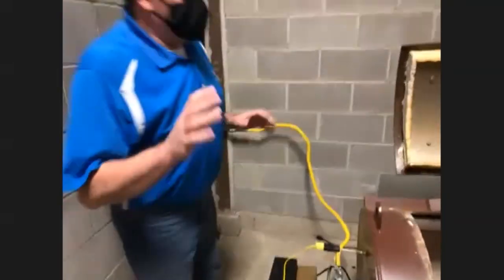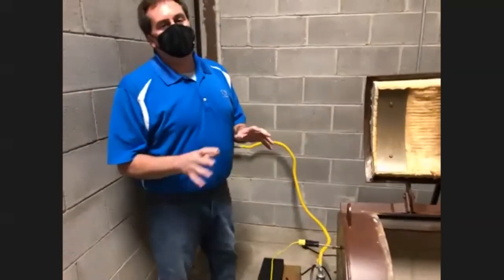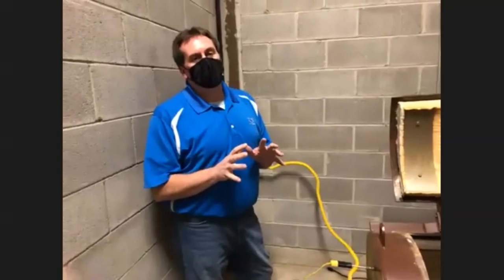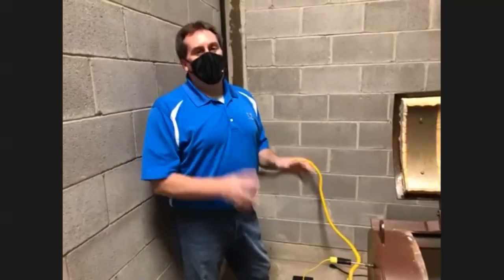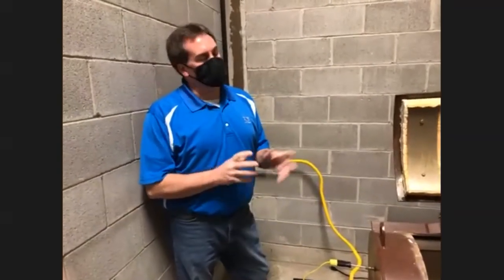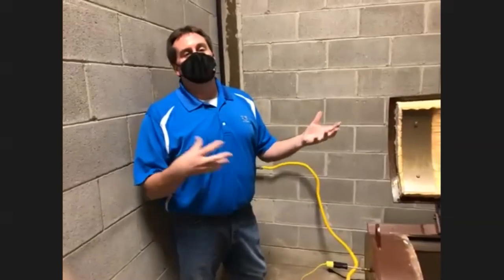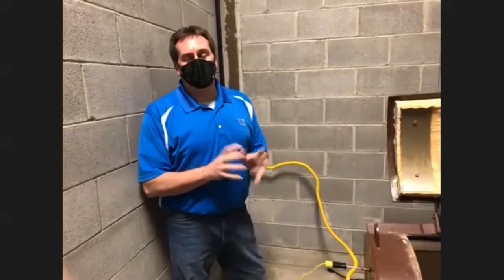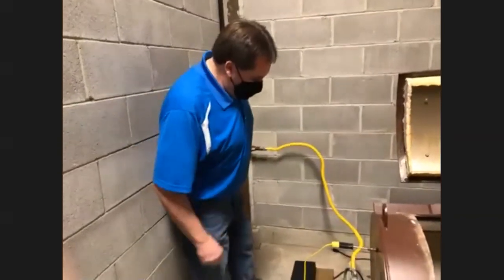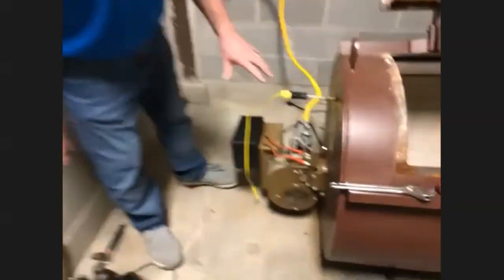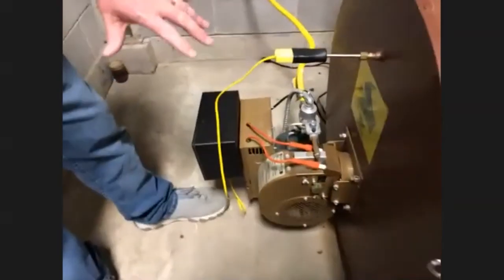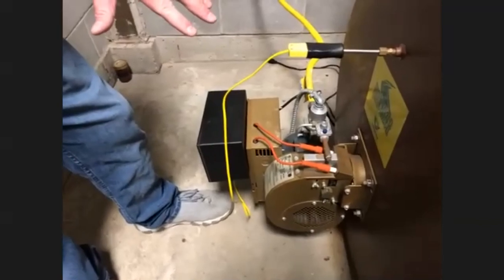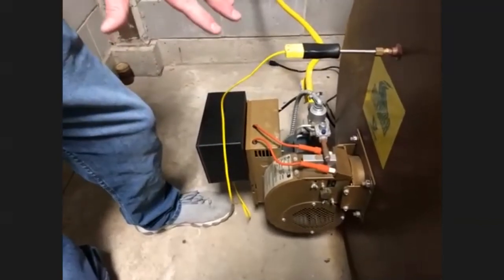And that is very important when you do that. Any gas appliance of any sort, always do a leak test. Because if you get any gas leaking, eventually you could have some serious issues later on with combustions. So as we go through here, again, we have the gas burner. And when these are shipped to you, there is a main gas port adjustment screw behind this cap.